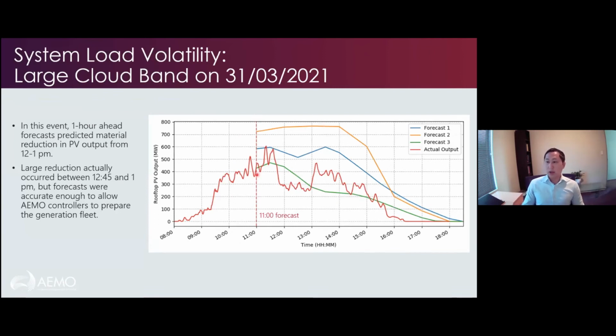So this is the hour-ahead forecast, and you can see here this forecast was showing quite a large drop between 12 and 1. The actual drop did occur a bit earlier, but it did give us time to actually prepare the fleet and make sure there were enough reserves to cater for this 300 meg deviation in rooftop PV output.